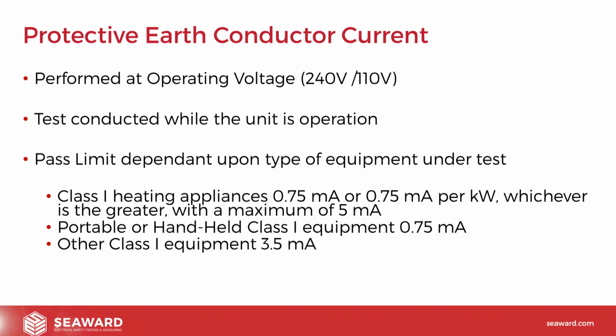Anything portable or handheld, so anything that's either designed to be in operation whilst you're holding it, or anything that's very easy to move around, would have a 0.75 milliamps limit. Now, when we're talking about handheld here, we're not talking about double insulated handheld equipment. This is anything that's earthed. Anything else, any other kind of class 1 equipment, would have a limit of 3.5 milliamps. That generally would be something that is either what we call transportable or stationary, something that's designed to be used in one place without moving around. It may have handles to transport it whilst not in operation, but it's typically designed that whilst it's in operation, it's stood in one place.